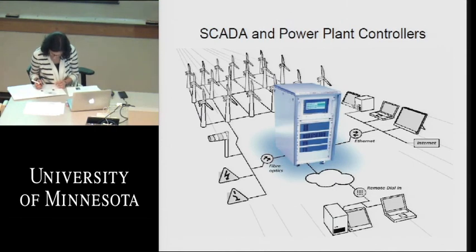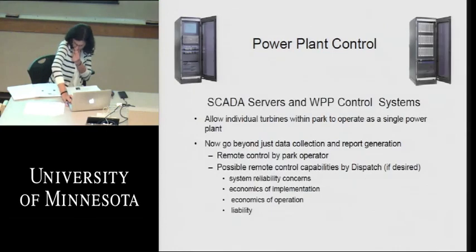As you can see, it's monitoring the wind turbines, the MET station, breakers, giving any cautions and alarms, and it's feeding the signal in and out to various interested parties who want to see what's going on in this power project. So the power plant controller really allows the plant to be run as desired, for system reliability concerns, economics, to make sure it's operating as efficiently as possible, and the operational economics as such.